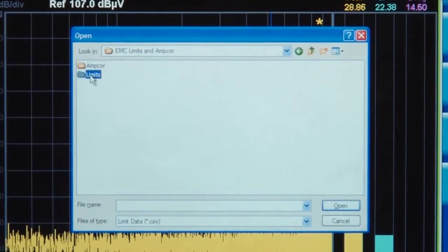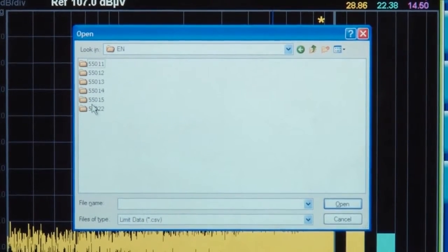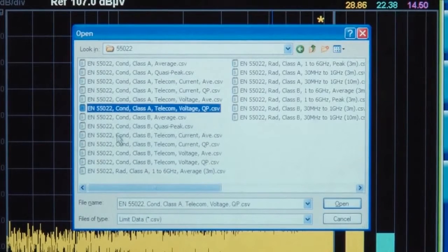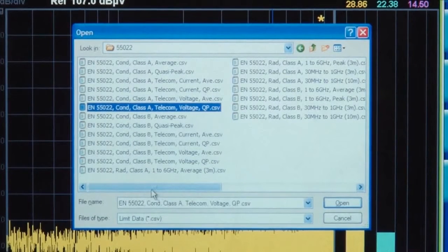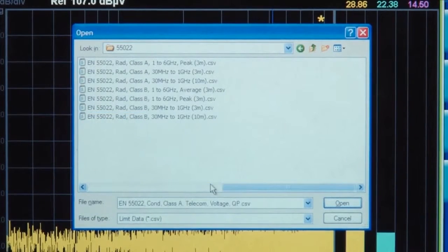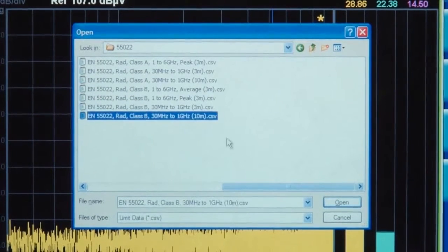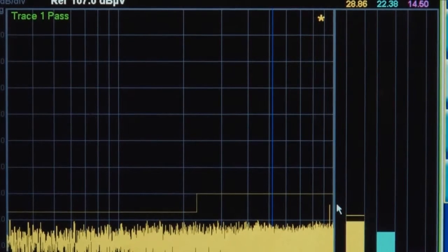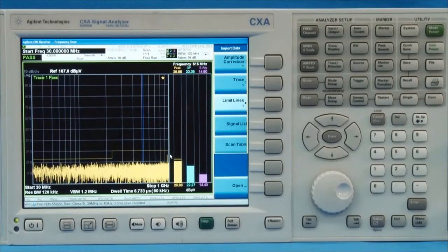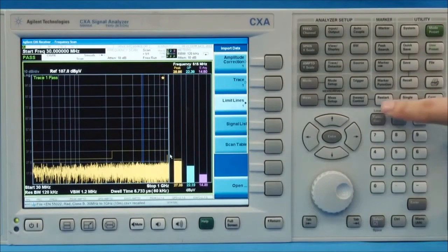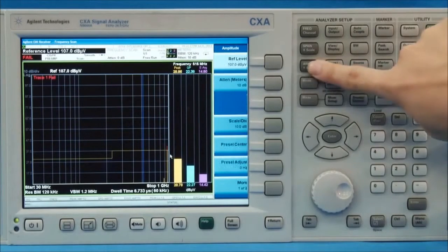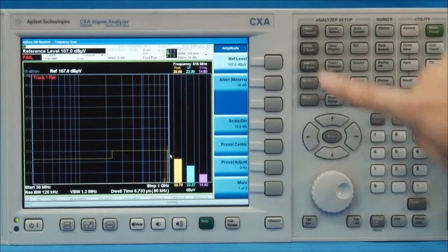In the near-field test, EMI standard test limits are not useful because of a number of factors that can affect the test readout, like the probe position and DUT shape. Now let's start the sweeping and adjust the reference level to better observe the signals.